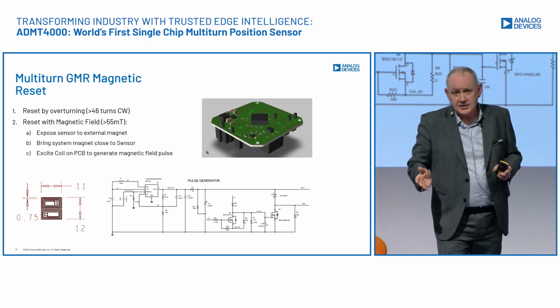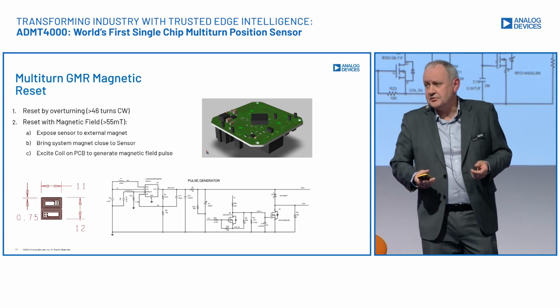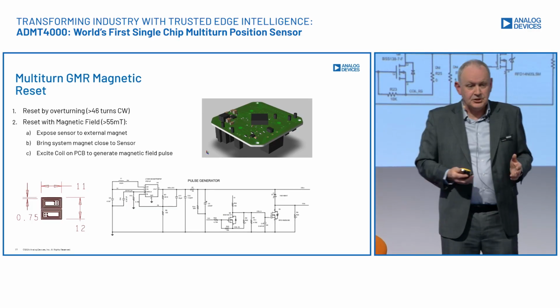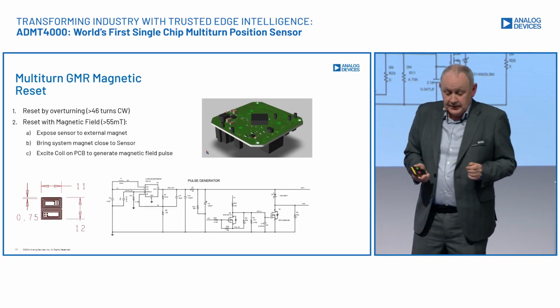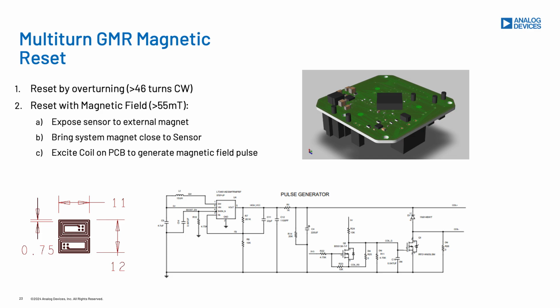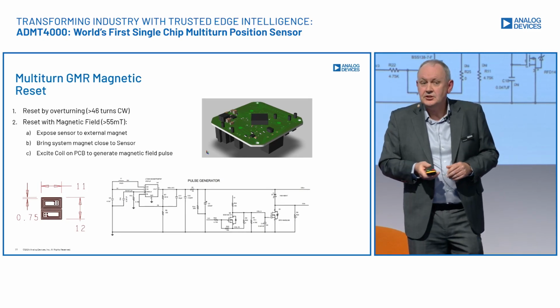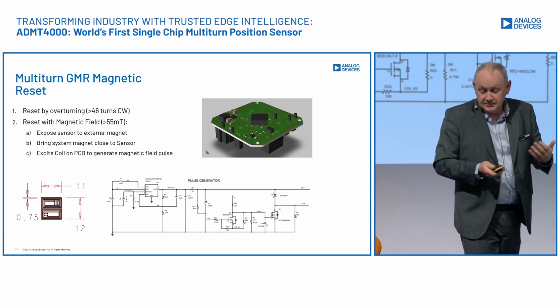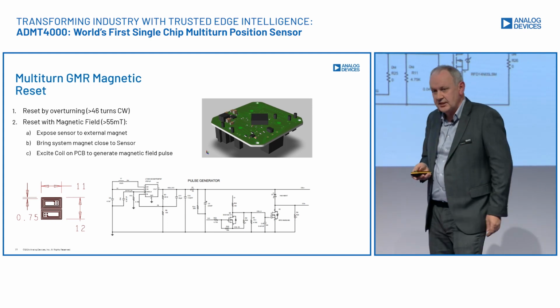The second way you can do that is apply a very strong magnetic field over 55 millitesla. That can be done with an external magnet. It can be done by bringing your system magnet that's already there closer to the sensor to make a higher field, and that'll reset the part as long as it's over 55 millitesla. Or finally, on the PCB, we can put a coil or give you a design for a coil which can be put on the PCB and energized externally with a very short pulse of current to reset the part as well. So they're the typical ways the product can be reset.